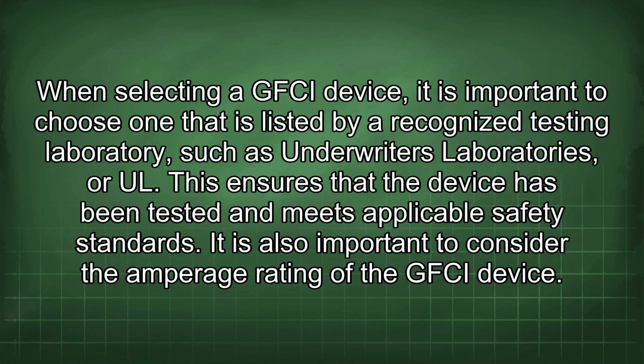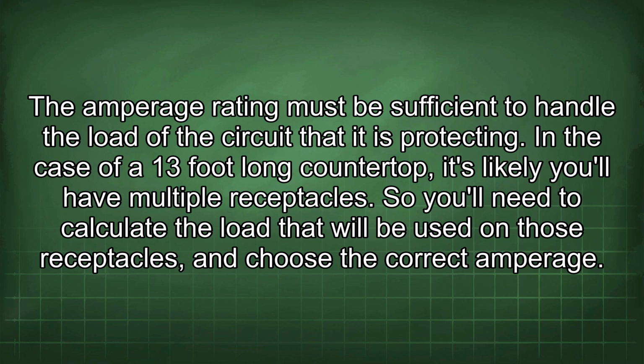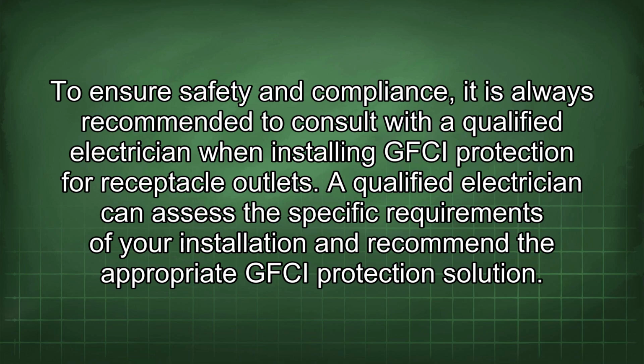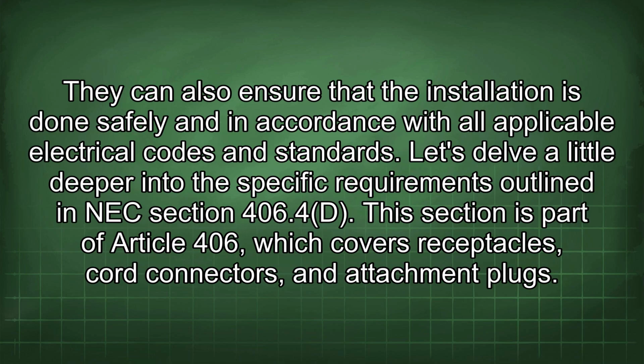It is also important to consider the amperage rating of the GFCI device. The amperage rating must be sufficient to handle the load of the circuit that it is protecting. In the case of a 13-foot-long countertop, it's likely you'll have multiple receptacles. So you'll need to calculate the load that will be used on those receptacles and choose the correct amperage. To ensure safety and compliance, it is always recommended to consult with a qualified electrician when installing GFCI protection for receptacle outlets. A qualified electrician can assess the specific requirements of your installation and recommend the appropriate GFCI protection solution. They can also ensure that the installation is done safely and in accordance with all applicable electrical codes and standards.